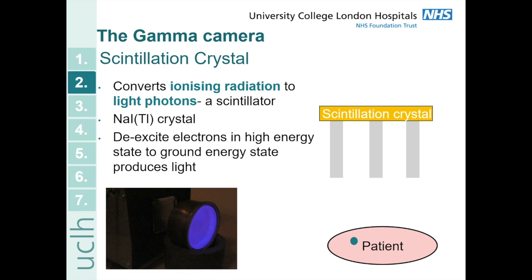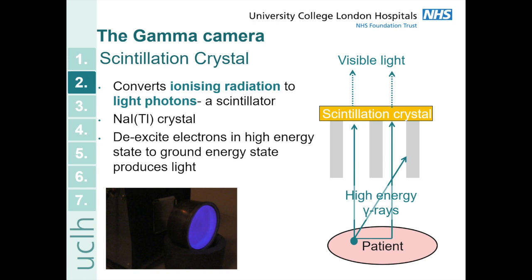The next part of the gamma camera is the scintillation crystal, which converts the incoming ionizing radiation into light photons. Generally in nuclear medicine we use a sodium iodide crystal doped with thallium. It works by de-exciting electrons in the scintillator from a high energy state to a ground energy state, which leads to the production of visible light. The important thing is that high energy gamma rays coming in from the patient are converted into visible light, which then goes into the next stage of the detector.